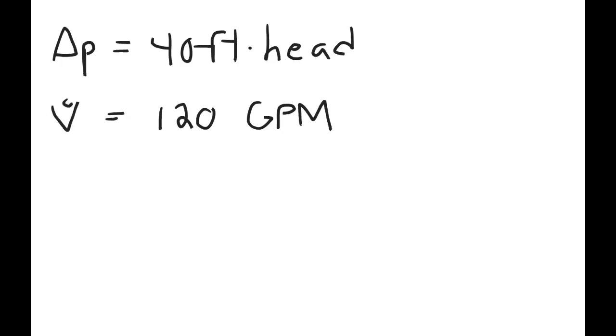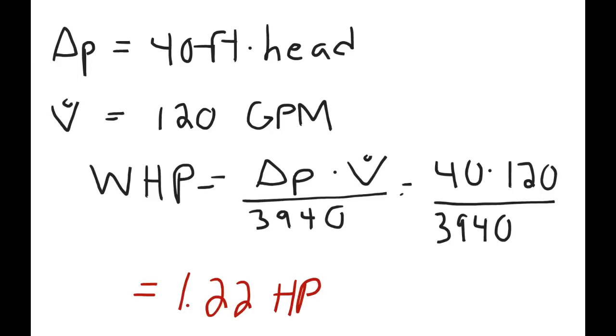To find the water horsepower or the output of the pump, you have to use the working equation. WHP equals delta P, which is the change in pressure, times the volume flow rate, 120 gallons per minute, over 3,940. If we calculate the equation out, delta P multiplied by the volume flow rate over 3,940, the total output of the pump, water horsepower, is equal to 1.22 horsepower.